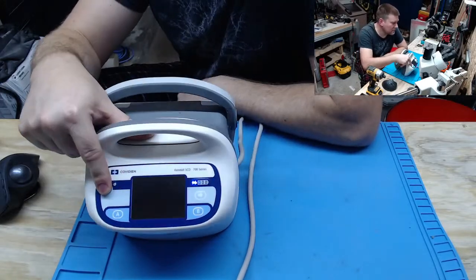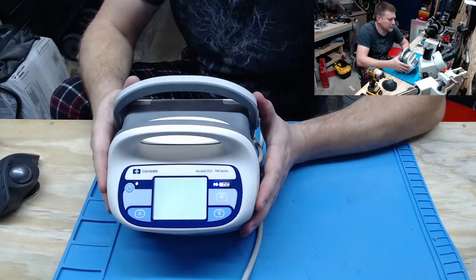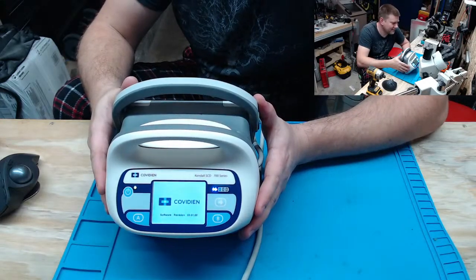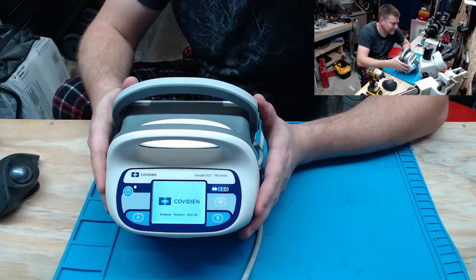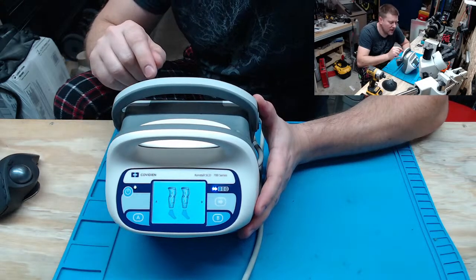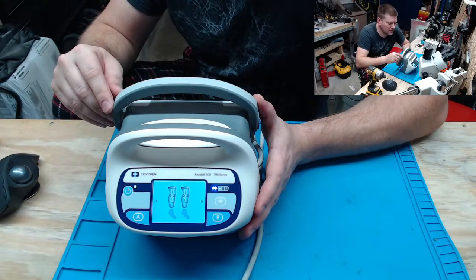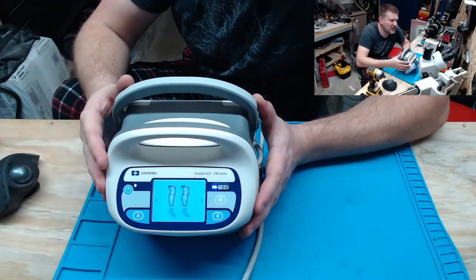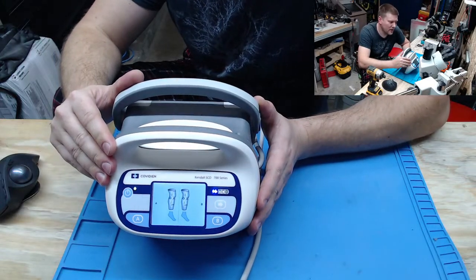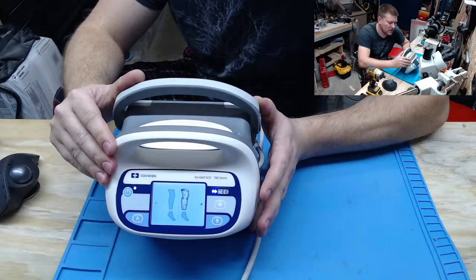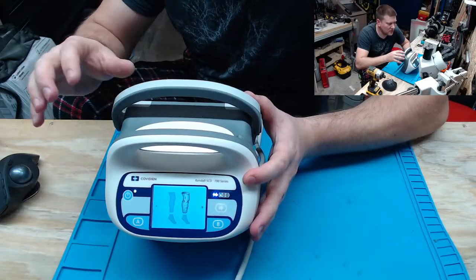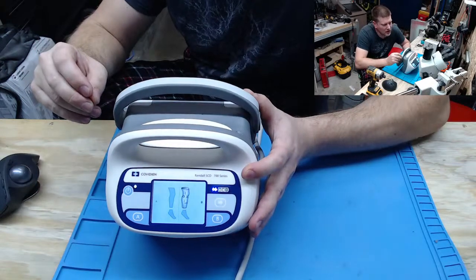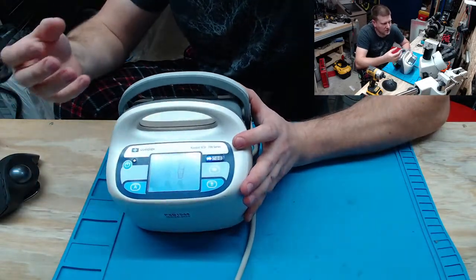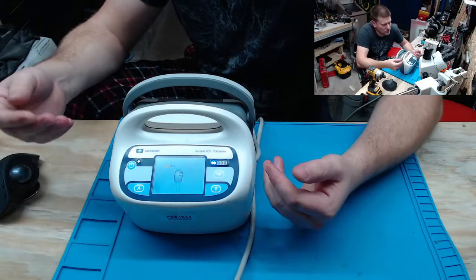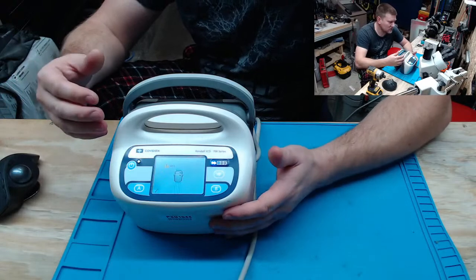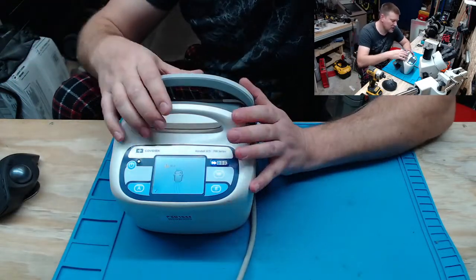So I'm going to boot it up. I'm going to show you guys what it does. You can hear it testing the relief valves. It tests the motor to make sure it's not bound up, and now you can see that it's actually seeking to see what type of sleeve is on the patient. So it's inflating certain chambers under a certain amount of time, and based on the amount of time and the pressure that it reads back, it knows exactly what type of sleeve you put on. If it's an arm sleeve, if it's an anklet, if it's a leg sleeve.